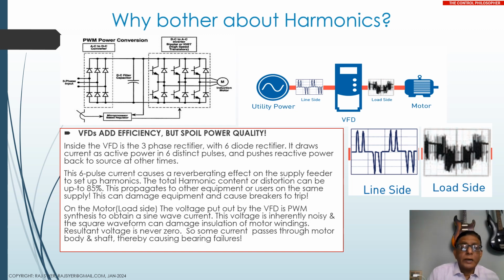On the load side, as I explained earlier, the pulse width modulation synthesis is basically a series of square waves, and a square wave by its very nature does not have a gradual rate of change of voltage. It is a very rapid change in voltage, and at 415 volts these are quite high, very high dV by dt. Actually, for three-phase 415 volts, the DC bus is switched at about 530 volts or so. So this again can stress the insulation of the motor.